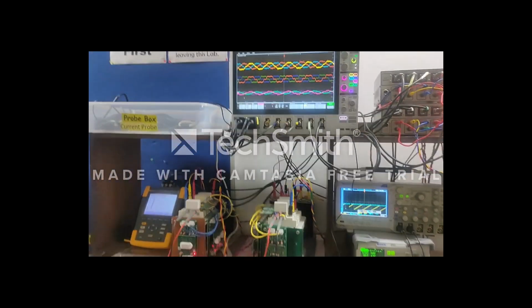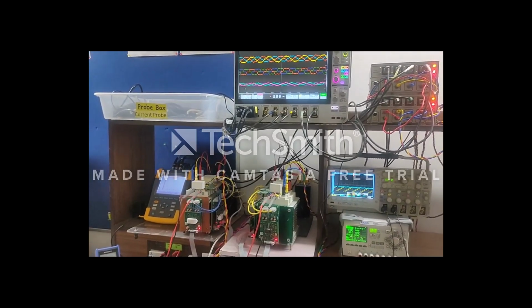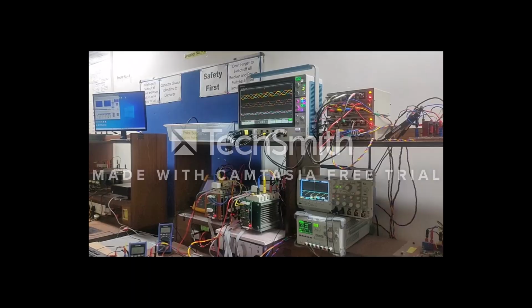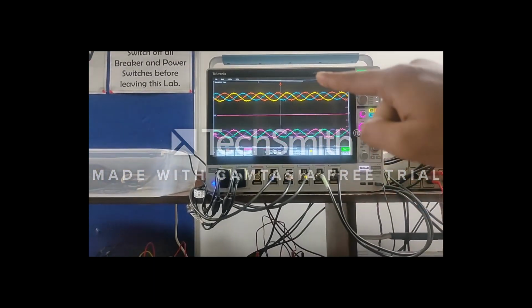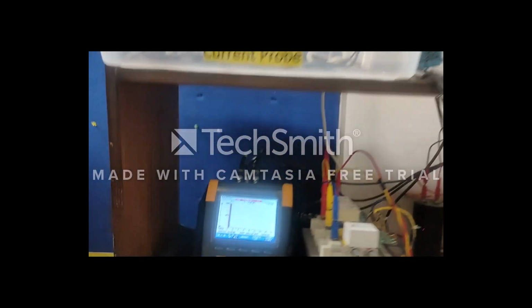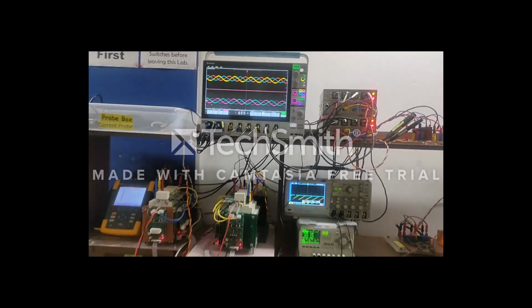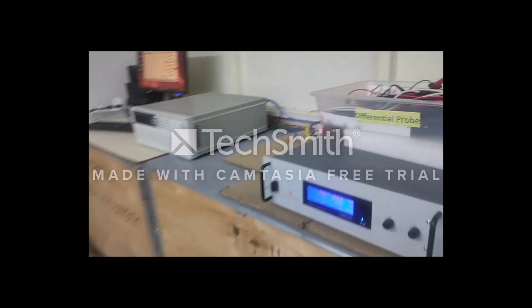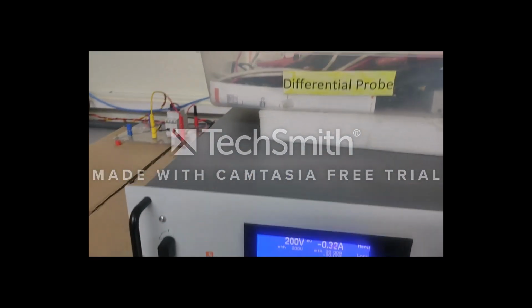So this is the main advantage in the mode 3 operation. We can inject the total power from the first inverter, and if there is no power, we can charge the battery using the mode 3 operation. If we turn off the non-linear load, the non-linear load current becomes totally zero. Whatever the available power at the sources, it will start injecting into the grid. You can see the THD of the current is around 5%. In this condition also the battery will charge from the available power at the first inverter and grid. You can see the current going into the battery is minus 0.25. It starts charging, and the SOC increases from 30% to 44%.